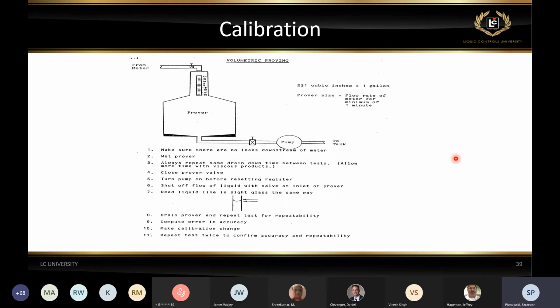There are some important things when you're using a volumetric prover. I talked earlier about wetting down the prover, making sure that the prover comes to the temperature of the liquid, and making sure the system is full of liquid. So you close the valve, you engage the pump, you charge the system, and then reset the counter. You want to make sure that you start your calibration process with the register indicating 0, and then again, fill up the prover, make the readings, and make the adjustments. And again, you may have to make multiple runs in order to check for repeatability, make an adjustment, change the calibration adjuster setting, make the meter accurate, and test it again for repeatability. It's a very simple process in a way. It gets a little bit more complicated, maybe especially on LPG, when you're dealing more with pressures, temperatures, and other factors.